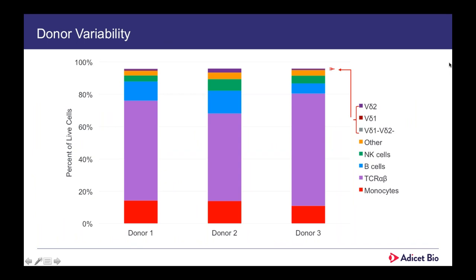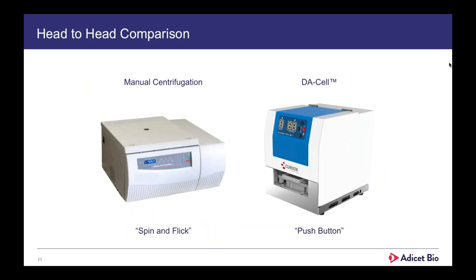Prior to implementation of the DA cell, we looked at donor variability of the material. Three different donors show high variability in many starting populations. Most starting material is high in monocytes and TCR alpha-betas. The gamma-delta population within all live cells is relatively small — less than 2% of all incoming material — and we need clean resolution on this population to ensure we're manufacturing the right cells for treatment of patients. This is the crux of the rest of the presentation: how do we compare a manual centrifugation method to this new DA cell?